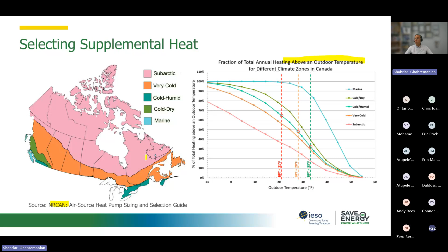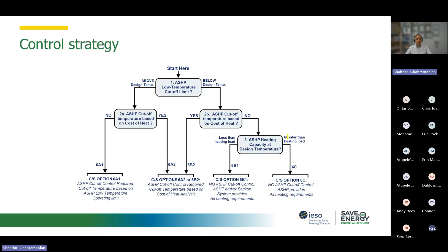Again, the control strategy becomes important. If we need supplemental or auxiliary heat, then the control strategy becomes a big component, in how the contractor or the trades that come and install it set up that control. Where is the point that the heat pump should be turned off, and our auxiliary heating system should start actually? So that's the control system that becomes important. And then they should have, similar to this, a decision matrix. They set it up on both the heat pump and the other auxiliary heating system that we have actually.